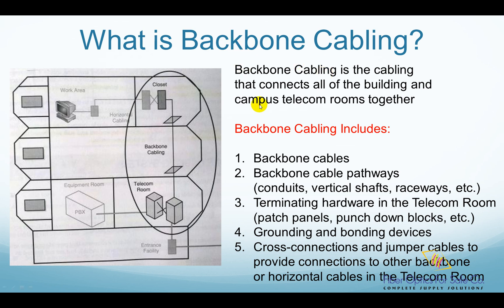The subsystems include the work area subsystem, horizontal cabling subsystem, backbone cabling subsystem, telecom rooms, equipment rooms, and entrance facility. In this video I will explain the backbone cabling system. Backbone cabling connects all of the building and campus telecom rooms together. It is also called vertical and riser cabling because it is usually installed vertically in the riser shaft to connect telecom rooms together in a multi-story building.